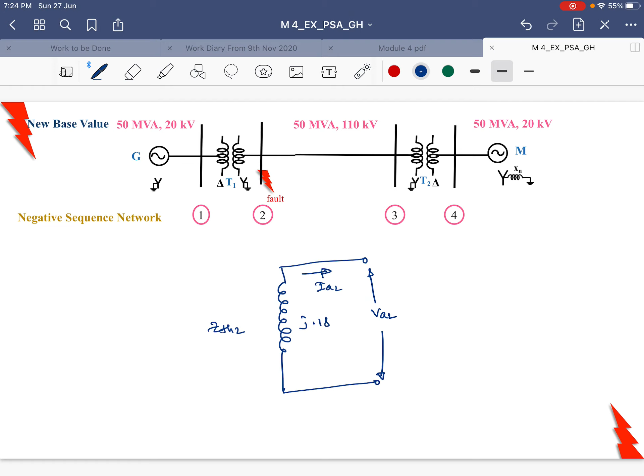The next thing is that you have to draw the zero sequence network for the given network. First start with the reference here. Carefully you have to draw it, based on the star delta transformer connections and other things. First look into the generator which is grounded, therefore it is starting from the reference point. This is also grounded. The motor is also started from the ground.